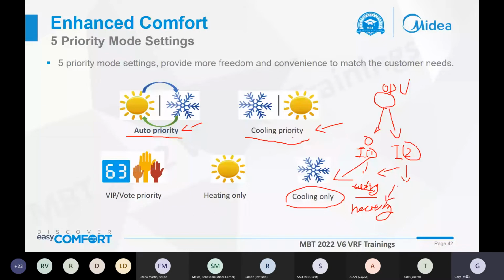Oh, sorry, it's not correct. Let me explain again. If you set the cooling priority, when the first unit is turned off and set to cooling mode, the second indoor unit can only run the cooling mode. When the first unit has run the heating, this one is turned on first in heating mode, and then I turn off the second unit in the cooling mode, and then the outdoor unit will run the cooling mode.